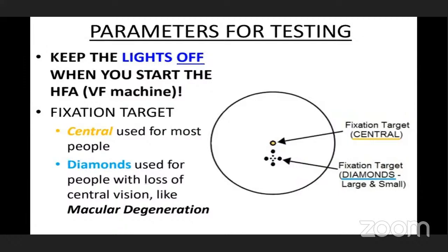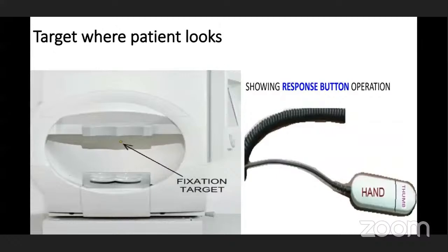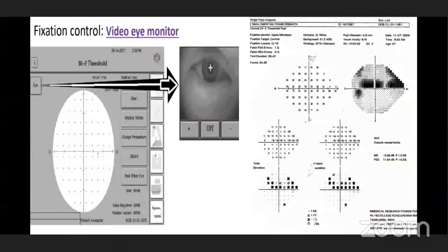The diamond fixation targets are used when there is any loss of central vision, such as macular degeneration. The patient looks at the fixation target and presses the response button whenever they see a light stimulus. The patient should be instructed to view the fixation target and not to look away from it at any point during the test.